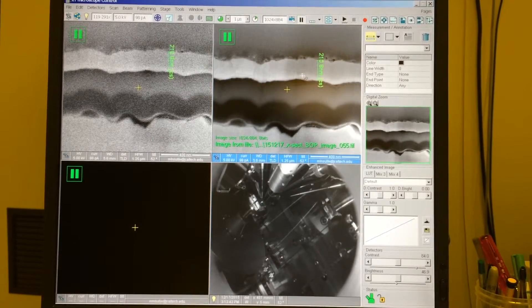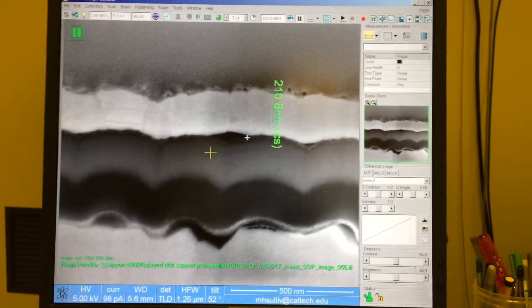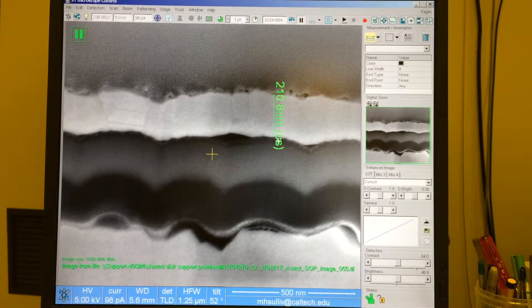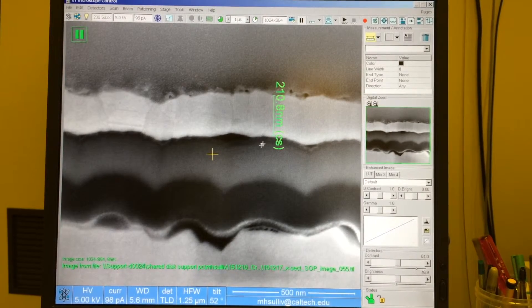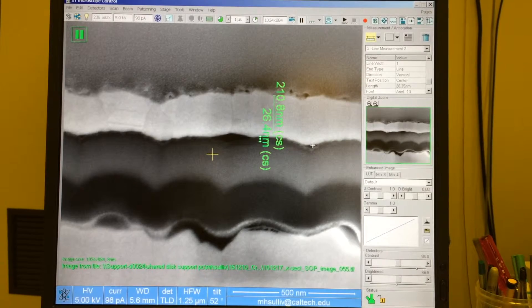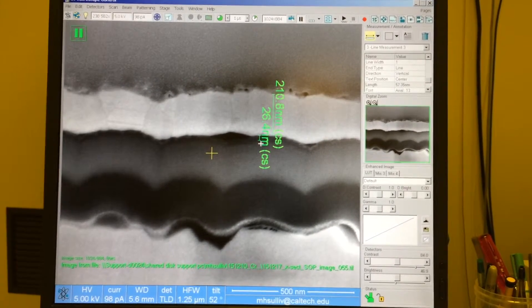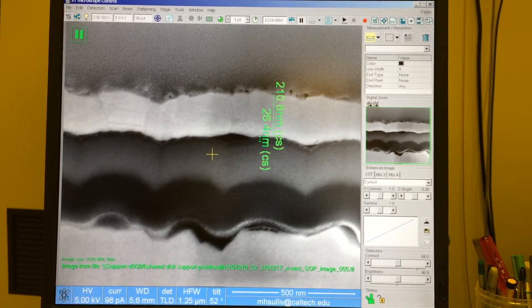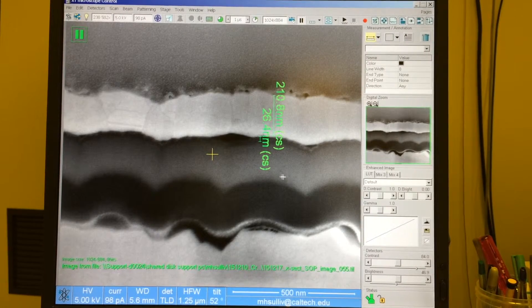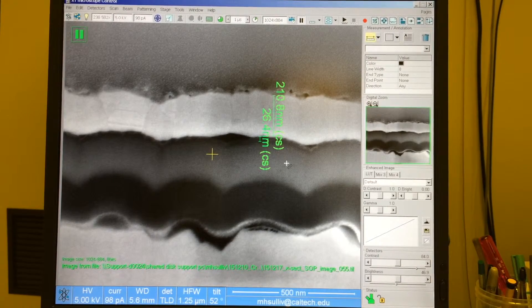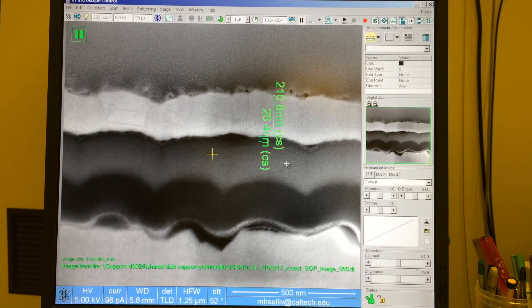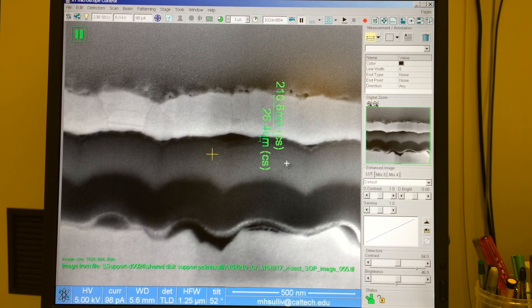When we know we can trust the long dwell time image, that allows us to make smaller measurements with confidence. So this is a particular layer I'm interested in. It's a little bit darker than the ones below or on top. So if we measure that, then we can see that I'm somewhere in the 20 to 30 nanometer range. Here it says 26. So I can be more confident with that when I know that my image is free of artifacts. So with that, that ends how to get a high-resolution image of your cross-section surface.